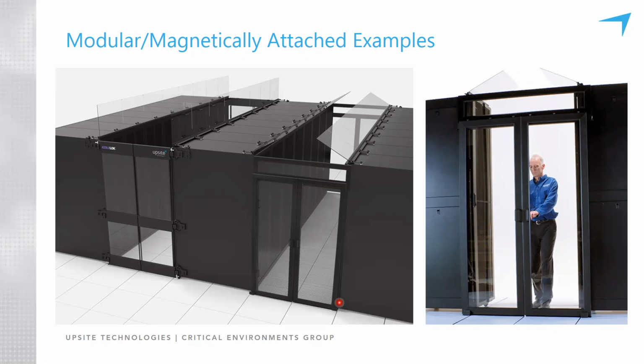It enables a row to be contained, doors to go up on a row before the row is built out fully. Say a row is planned for 15 cabinets on each side, and only 5 are in place. Well, you can put up a door and contain the 5 cabinets on each side. And then when it's time to add more cabinets to the row, take the doors off and add the cabinets, put them back on. Just takes a few minutes. The baffles that are sitting on top of the cabinets, we'll talk about those in a few minutes.